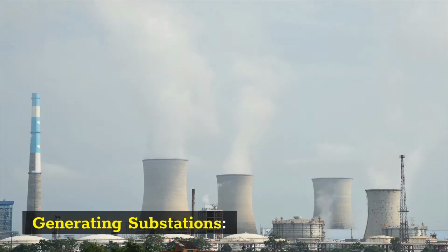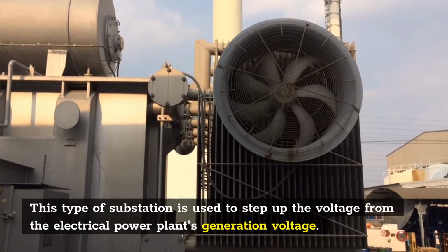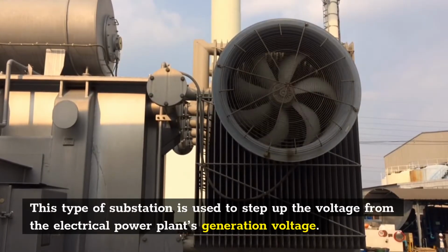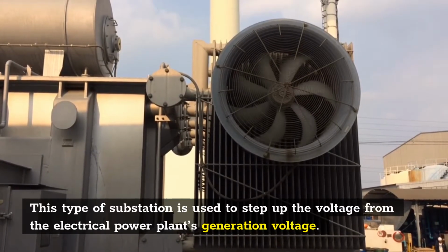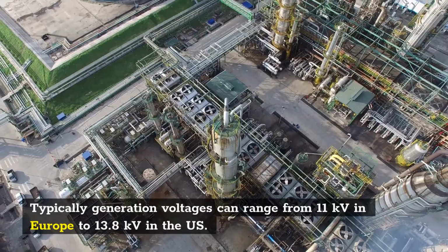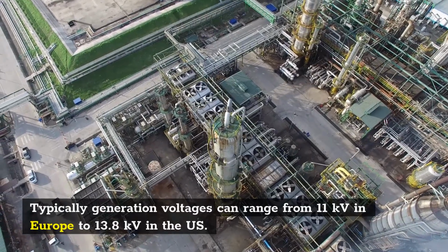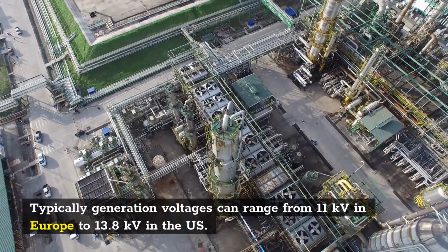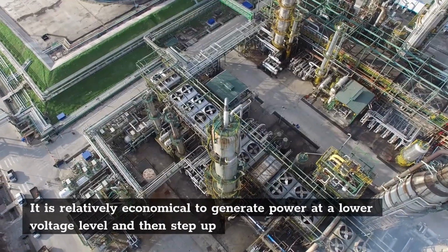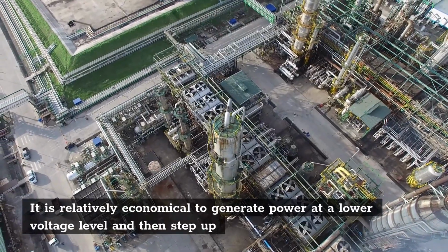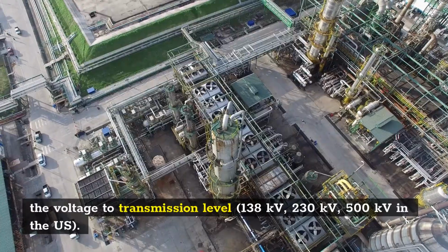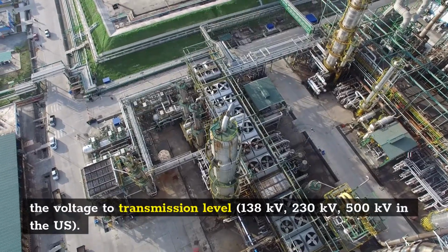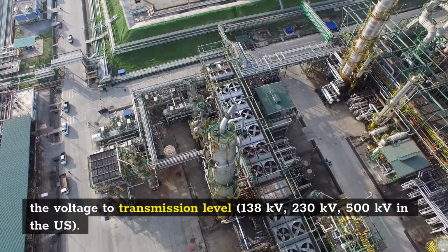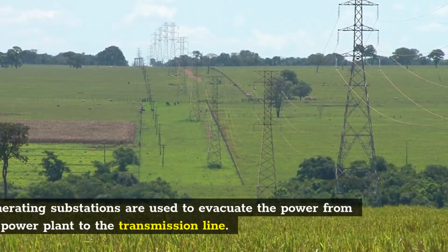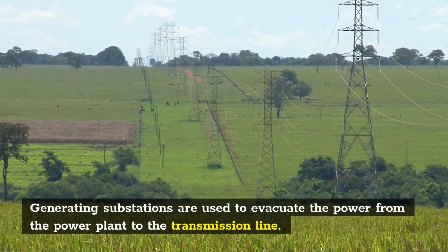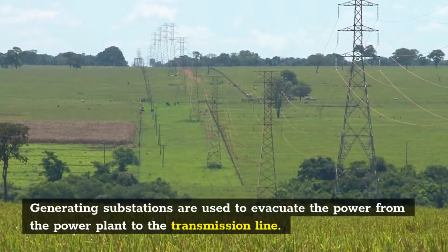Generating substations. This type of substation is used to step up the voltage from the electrical power plant's generation voltage. Typically, generation voltages can range from 11 kV in Europe to 13.8 kV in the US. It is relatively economical to generate power at a lower voltage level and then step up the voltage to transmission level, 138 kV, 230 kV, 500 kV in the US. Generating substations are used to evacuate the power from the power plant to the transmission line.